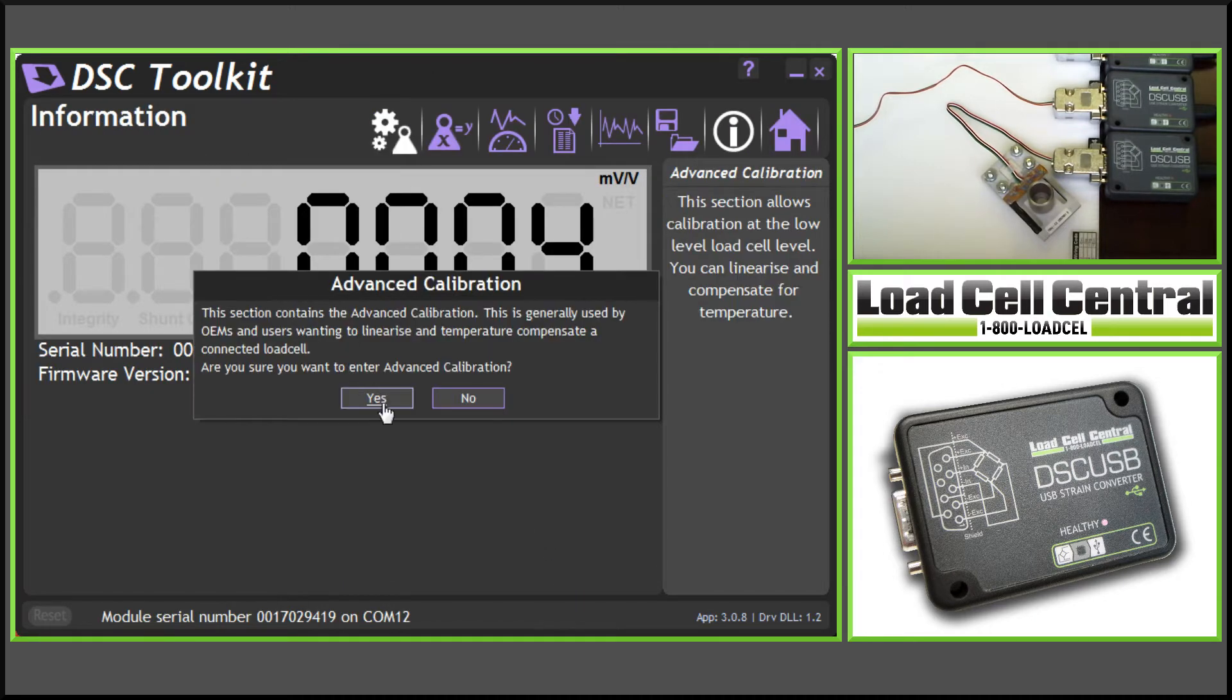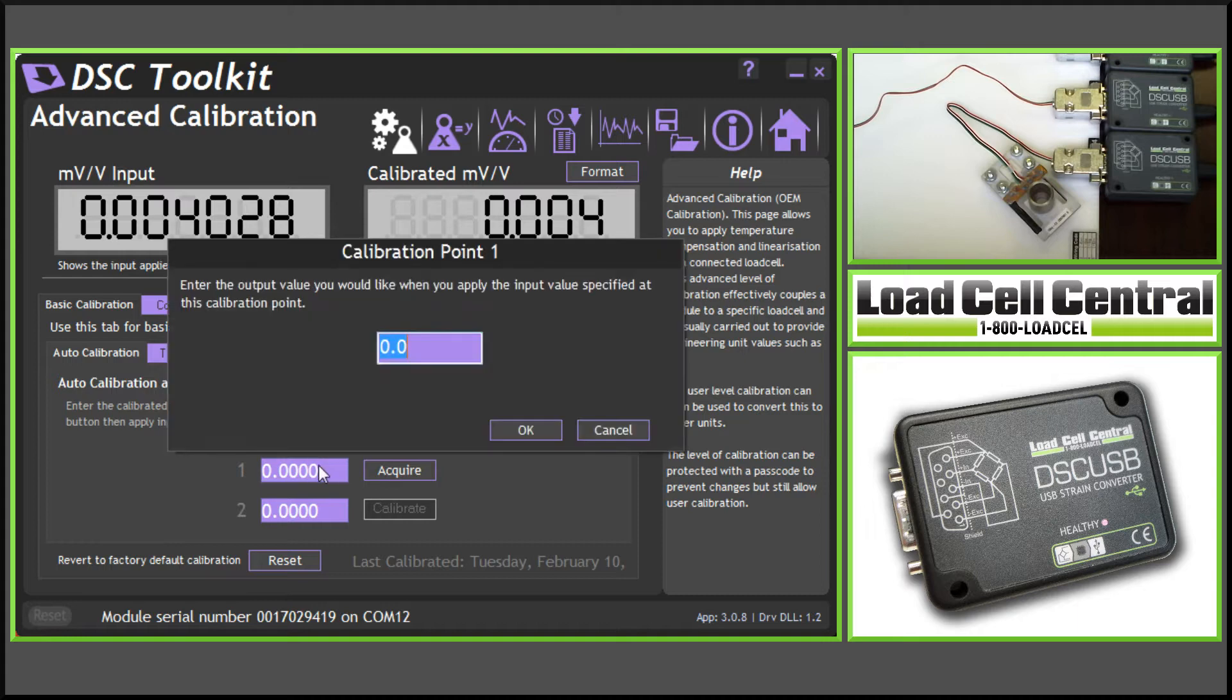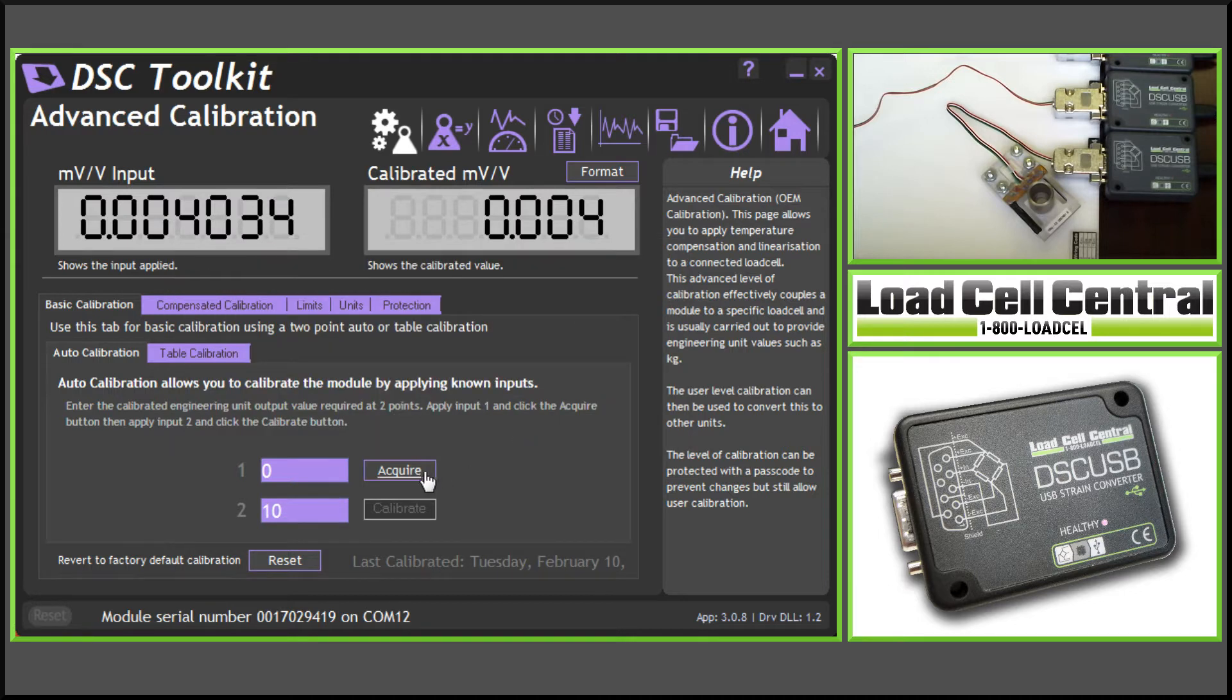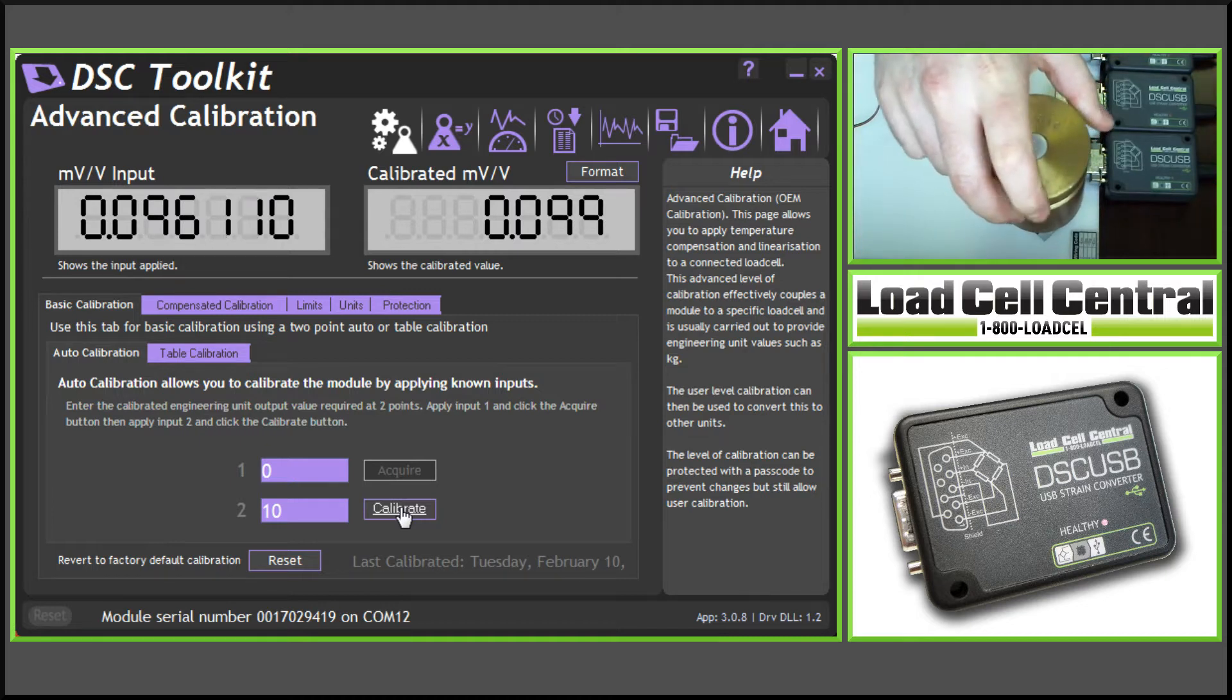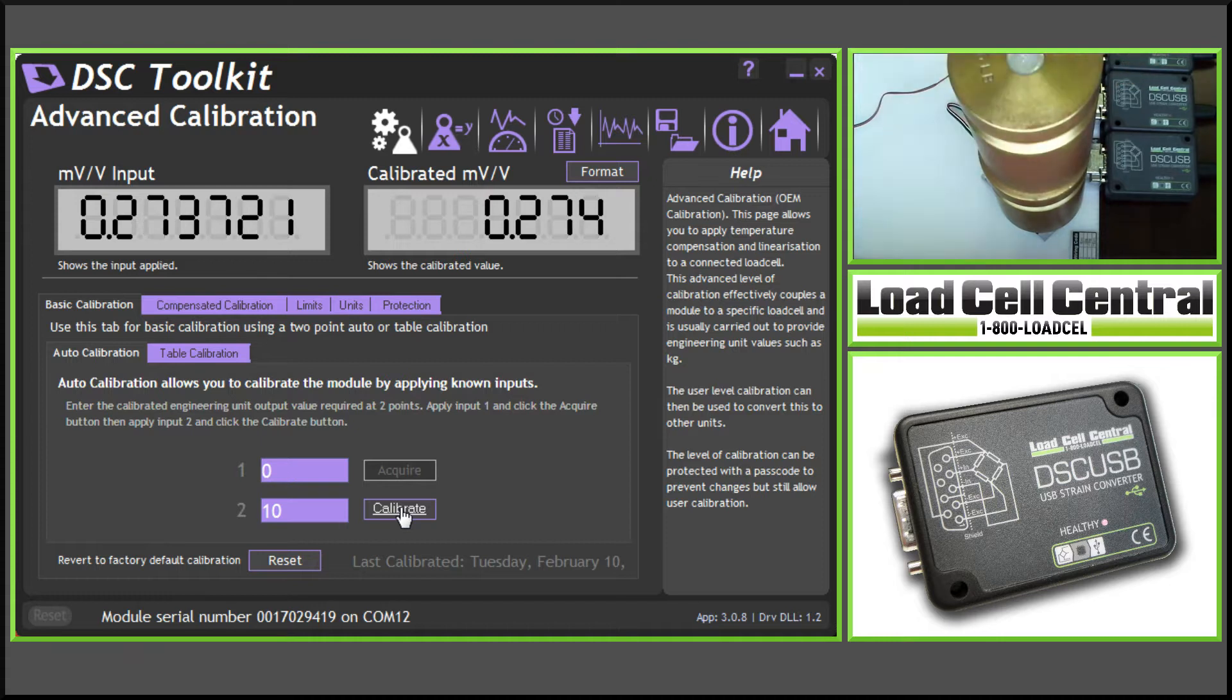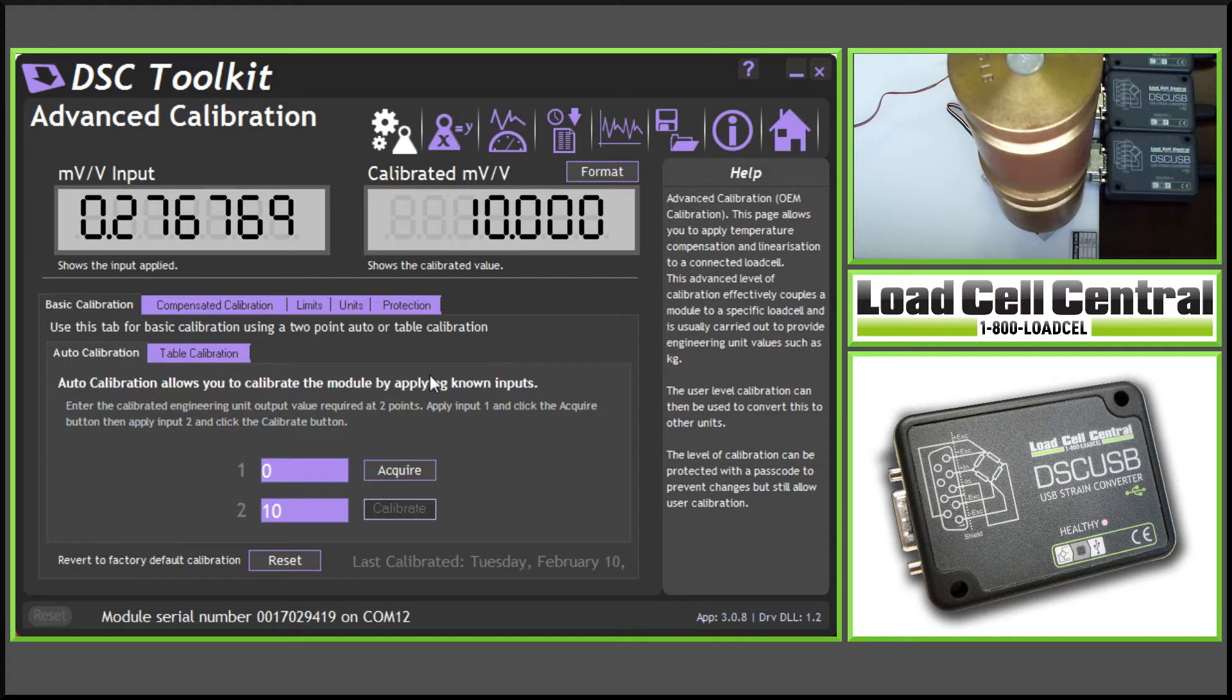The advanced calibration screen allows us to perform a live calibration. Here we can select the first point used, which would be 0 pounds, and the second point used, which will be 10 pounds. You can see in the top right my load cell is not loaded, so we can acquire the zero point. Now I have two five-pound weights. Once loaded, we can acquire the second point, and our load cell is now calibrated.